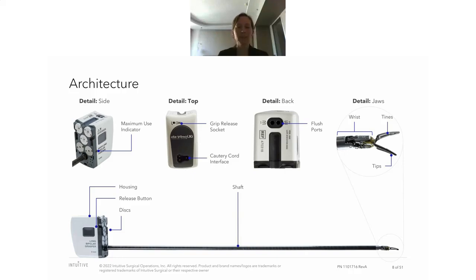Very important for reprocessing are the flush ports. There are 2 flush ports, 1 and 2. And then on the other side, you can see the tips. Obviously, the tip is different for each of the instruments, but the principle is the same. There's the wrist, which then leads into the tip. With all the thought that went into the design of those instruments to allow all those various features, there was also thought put into how we can reprocess them to make sure that they can be cleaned appropriately.